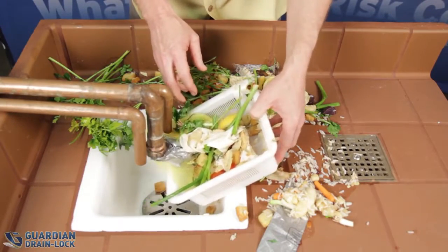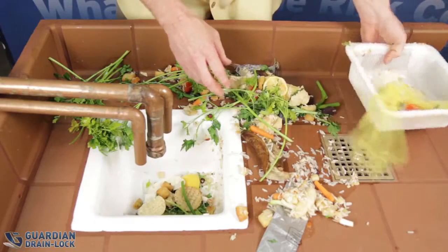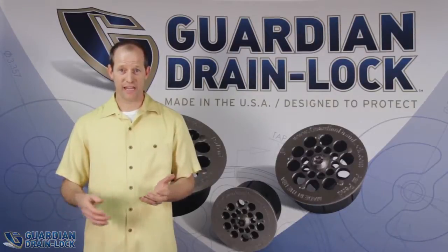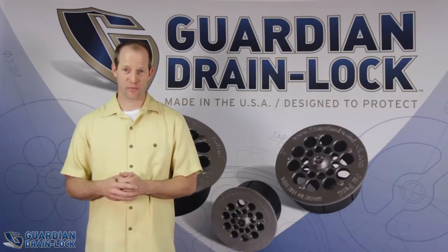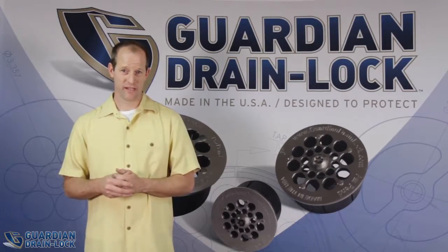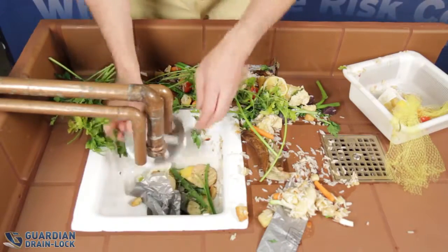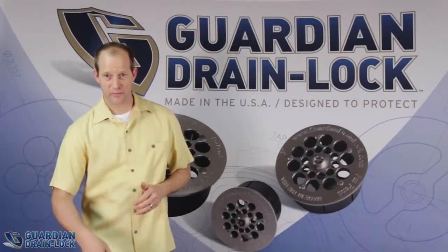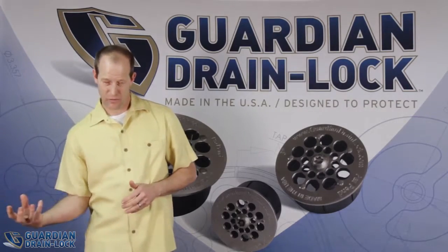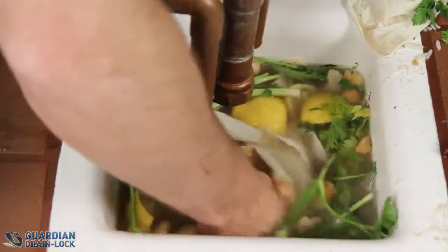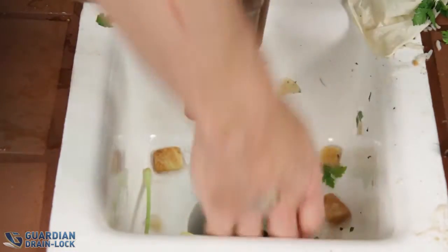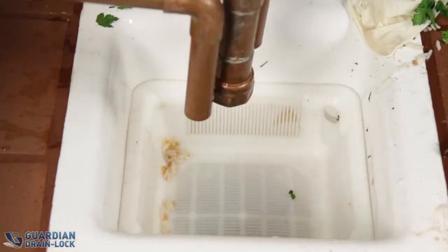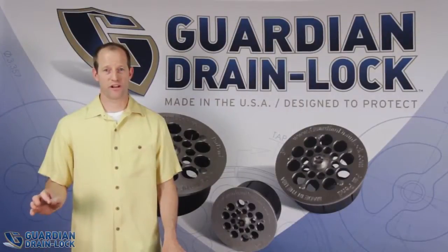So when the operator comes to service it, he can't pull the basket out and ends up dumping the product back into the floor sink, causing the floor sink to get filled. And in most instances, you'll find that operators think a floor sink is a giant trash can. So once they try to pull out the basket, they dump half of it back into the floor sink. They'll reach their hand in, pick up the strainer that holds it, remove it, have all the debris go down, and then they put the strainer and the basket back, and they think they solved the problem, but yet the problem is actually getting compounded down in your drain pipes for a bigger problem later to come. So the solution is to work off best practices.